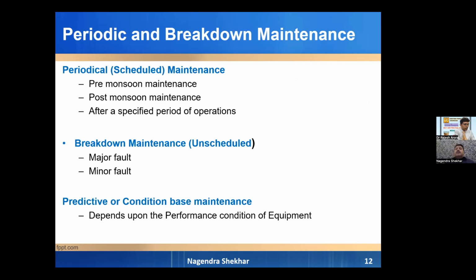For any distribution network in India, because we are a monsoon-hit nation, two scheduled maintenances are carried out for the distribution network, specifically overhead lines: pre-monsoon maintenance, then post-monsoon maintenance, or after a specified period of operations. Pre-monsoon, when we know there will be thunderstorms and rain, we must ensure the trees are not touching, and there should be proper sagging. Post-monsoon means when the rains are over, lines and poles must not lean after floods and heavy rains. These kinds of things happen. Sagging, broken conductors, loosened earth wires, loosened jumpers, and a specified period of operation, that is annually once in a year.